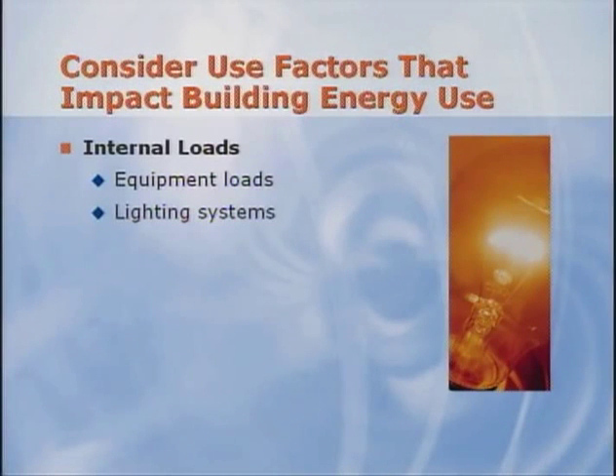Operational factors have a large impact on your energy consumption, whether your building is new or has been around for decades. Operating schedules cannot get you LEED credit, but are a huge opportunity to save energy in real life. In retrofit work, we have historically found more savings through proper scheduling than in any other energy savings areas. Proper scheduling for HVAC, lighting, and other energy-consuming equipment in the building is key. Matching system ventilation to the actual occupancy pattern of the building is another energy-saving area.